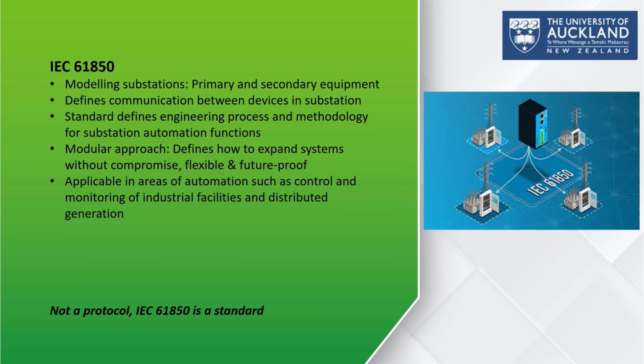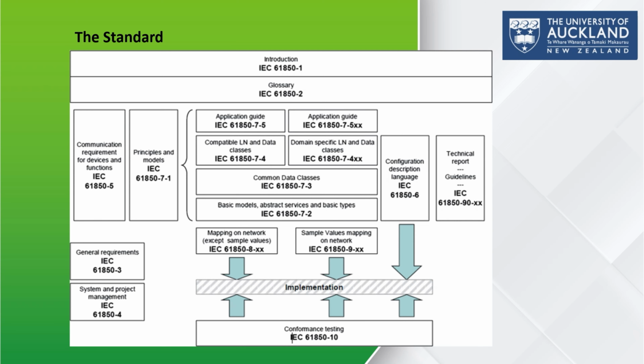So this diagram shows the overall structure of the IEC 61850 standard, which defines communication and data modeling for modern electrical substations. At the top, IEC 61850-1 and 61850-2 provide the introduction and glossary, forming the foundation for understanding the rest of the standard. The next group indicates general requirements, IEC 61850-3, and system and project management guidelines, IEC 61850-4, which describes how systems should be planned, engineered, and managed.